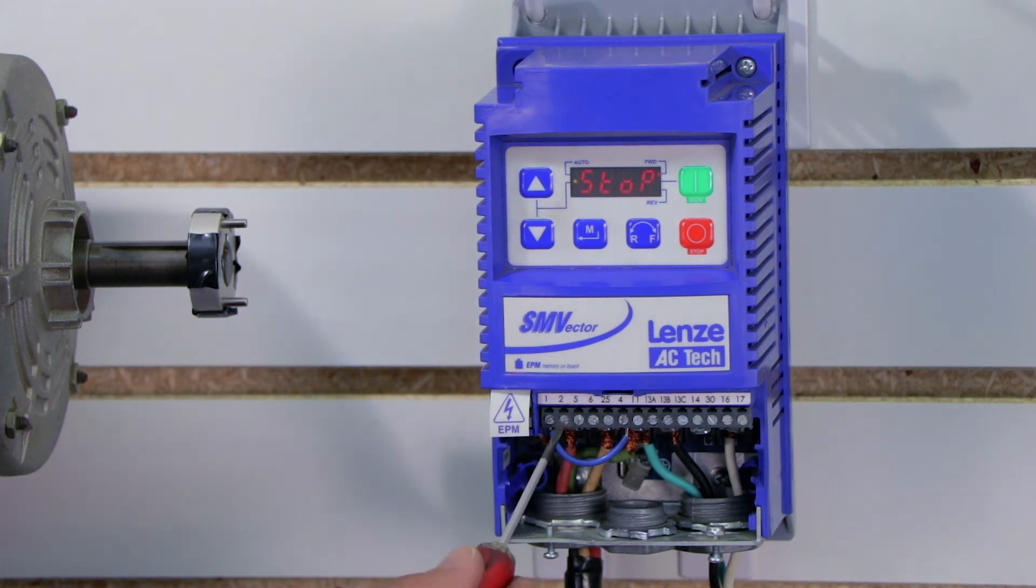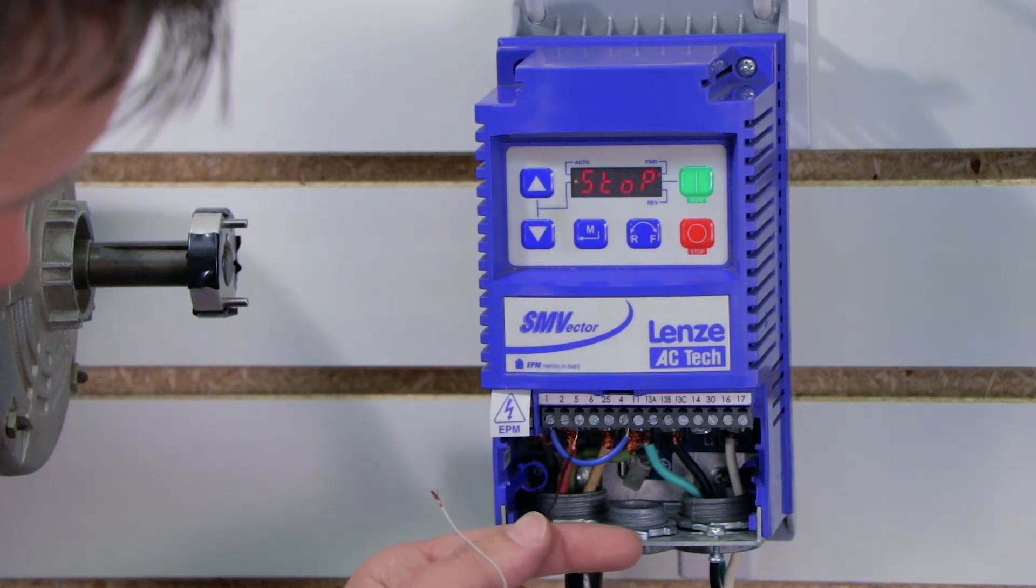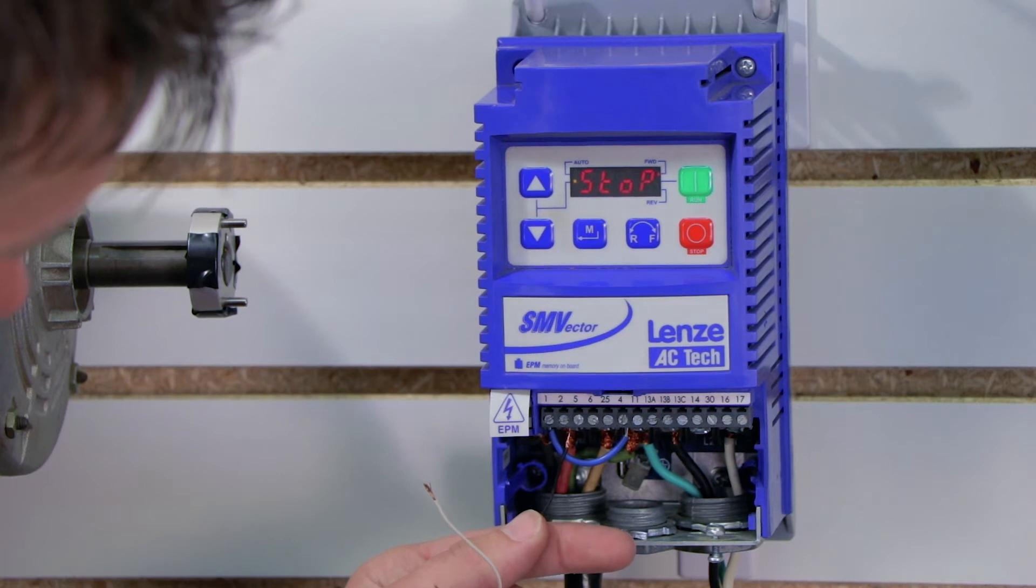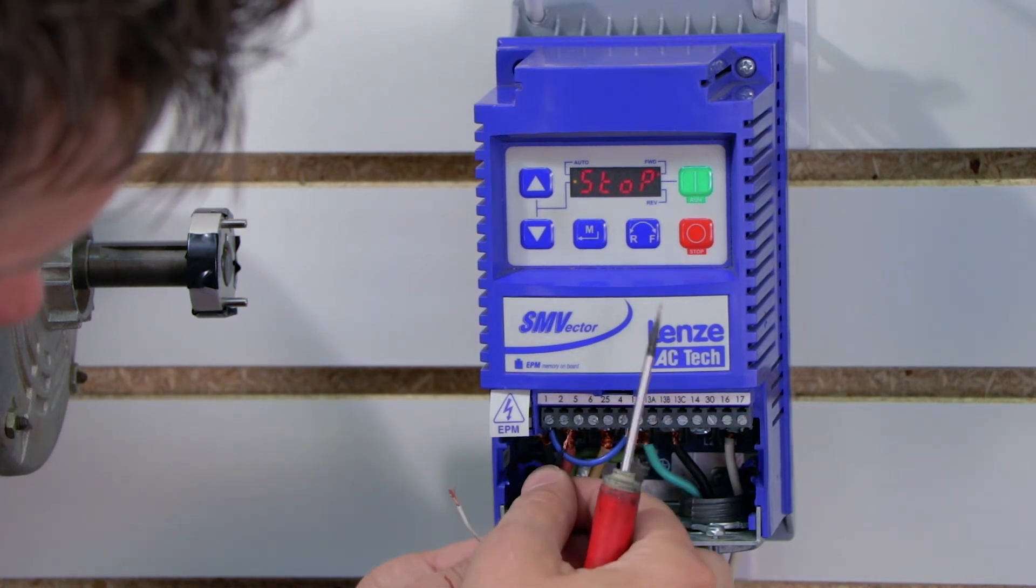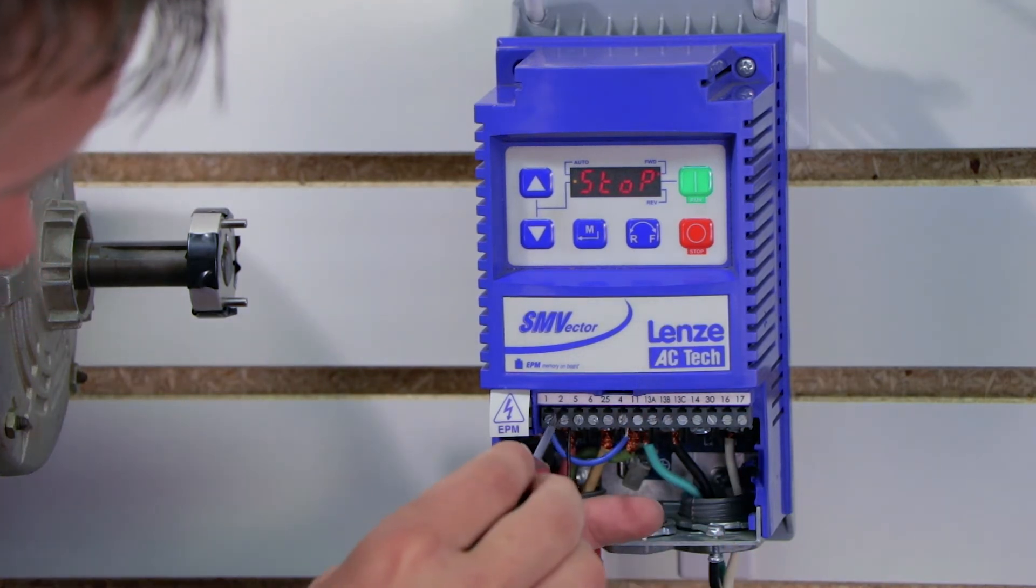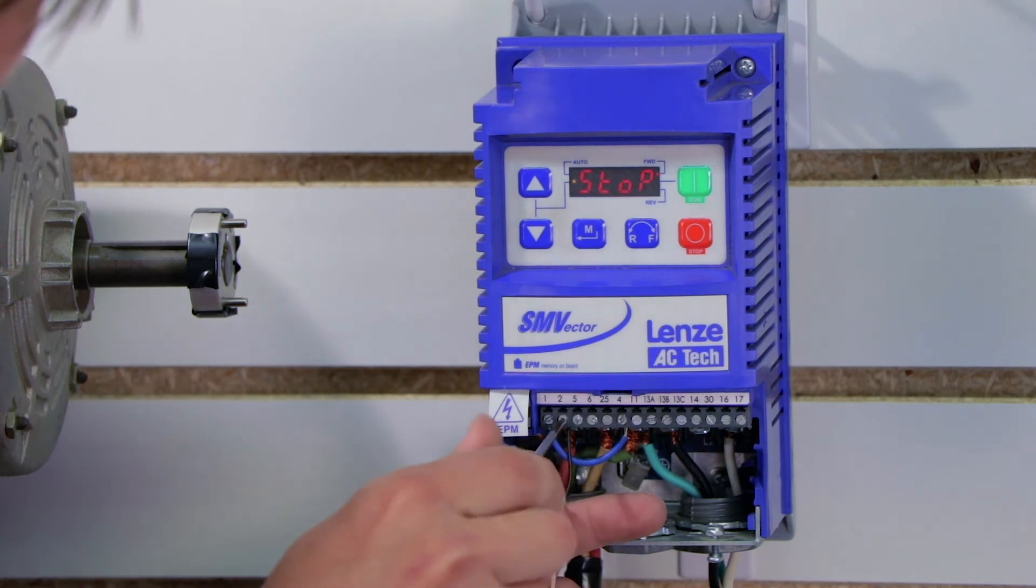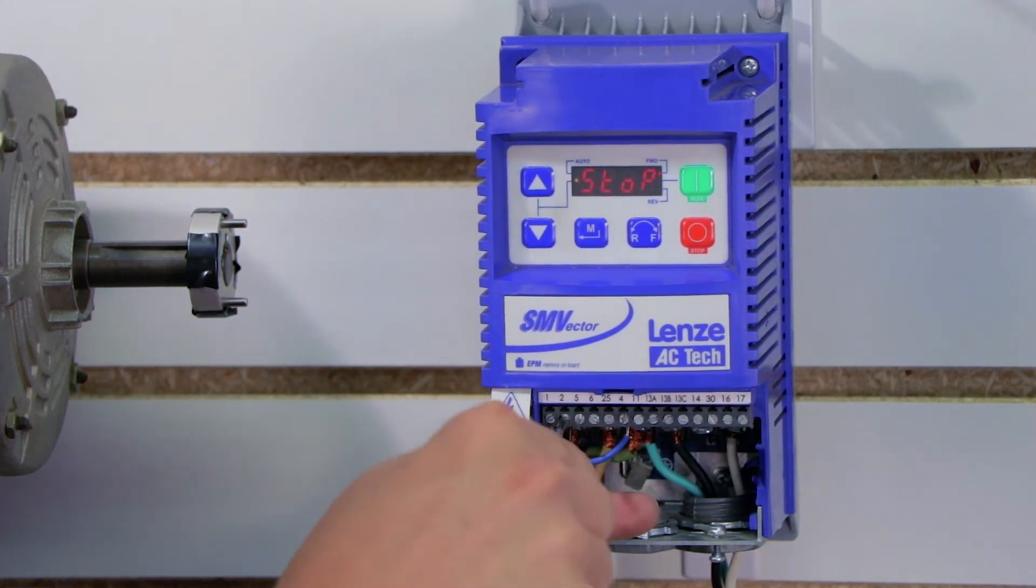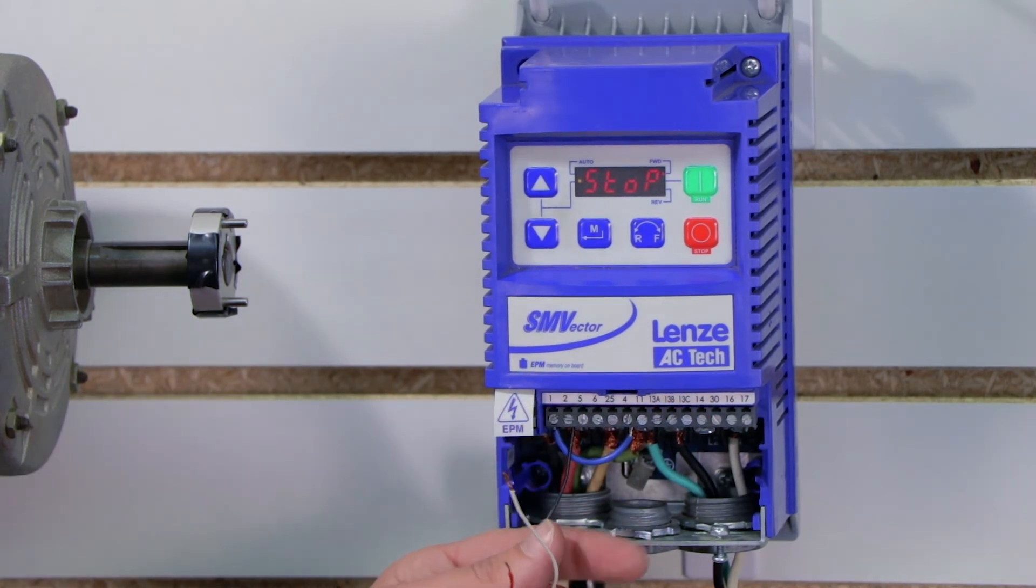Now as I said before, we're going to use terminals 2, 5, and 6. In the manual, terminal 2 is my common and as I said earlier we use black for the common so I'm going to go ahead and put black into terminal 2. It's a small wire, sometimes you got to wiggle it in there and then we tighten it. Don't over tighten it because you can actually strip out the screws which is never good.